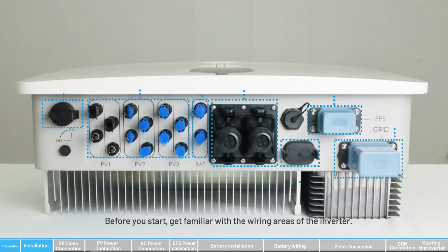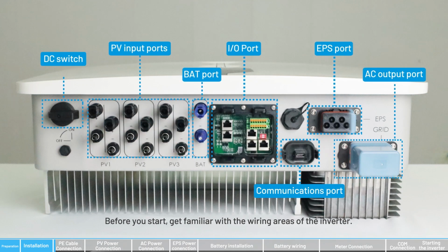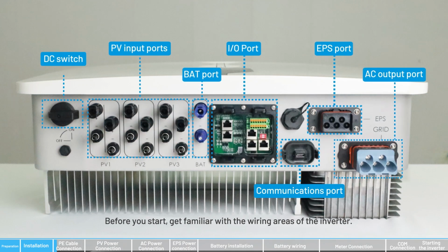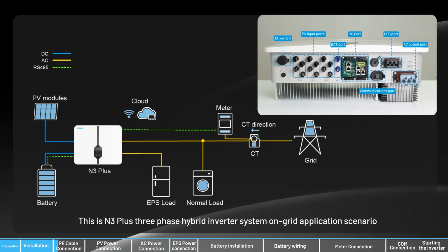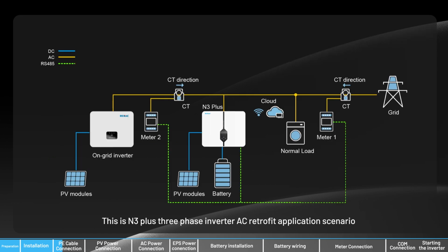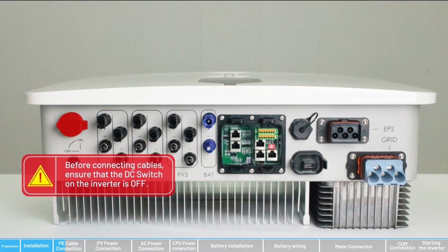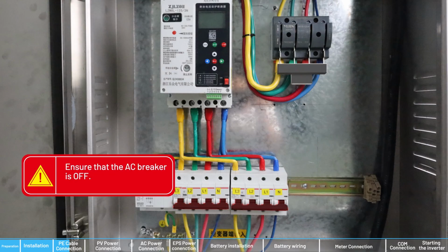Before you start, get familiar with the wiring areas of the inverter. This is N3 Plus 3-phase hybrid inverter system on-grid application scenario. This is N3 Plus 3-phase inverter AC retrofit application scenario. Before connecting cables, ensure that the DC switch on the inverter is OFF. Ensure that the AC breaker is OFF.